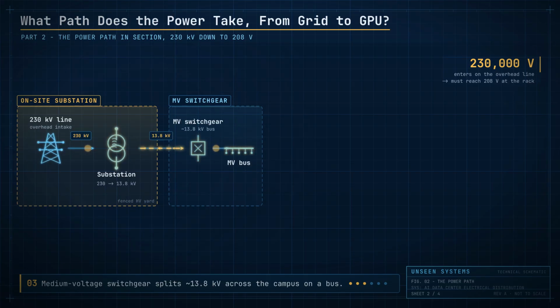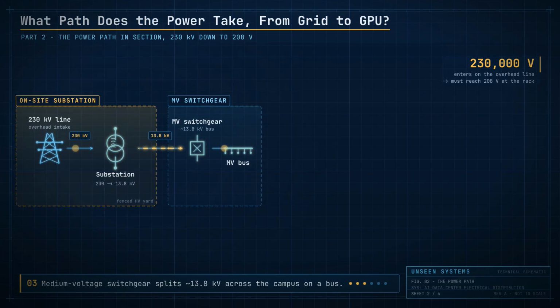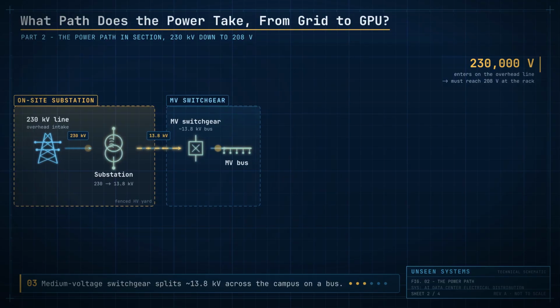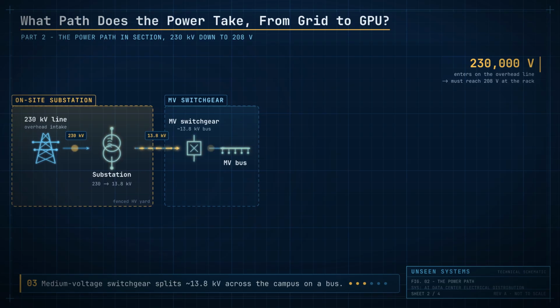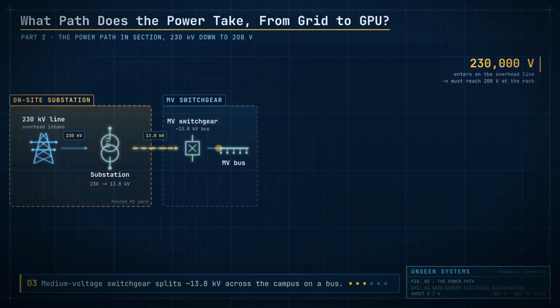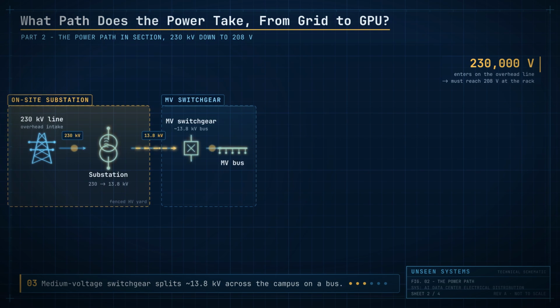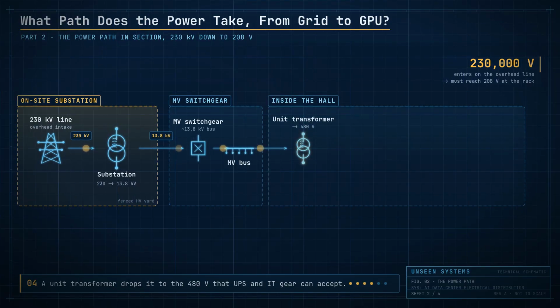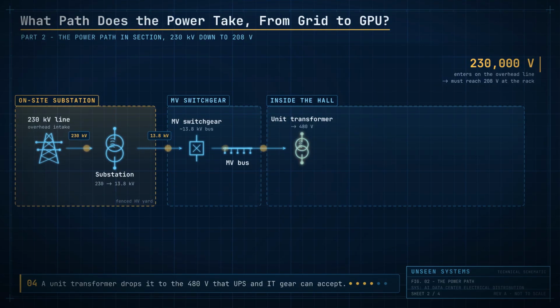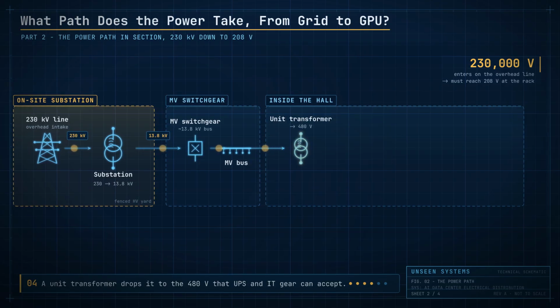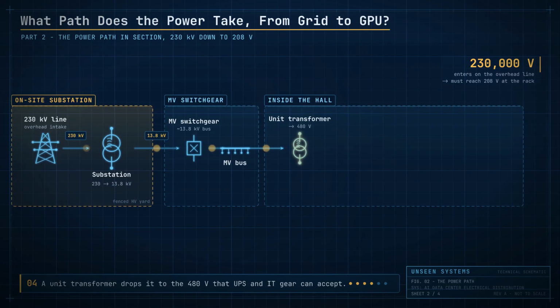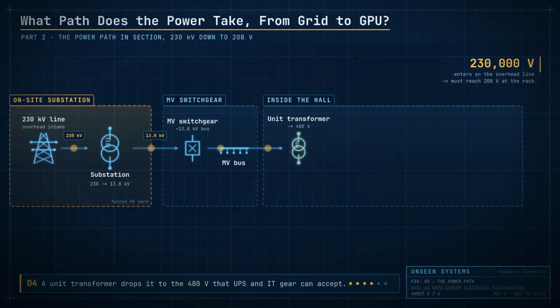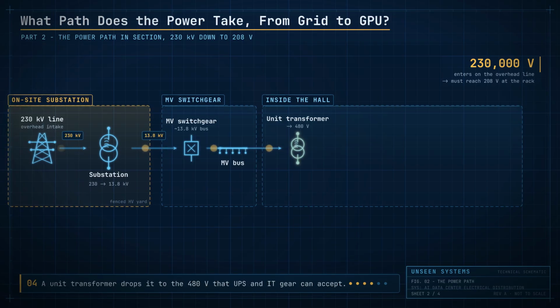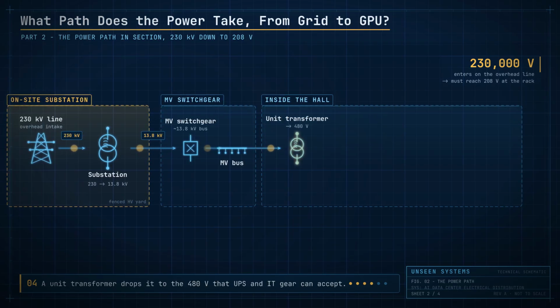Inside the medium voltage switchgear, that 13,800 volt supply is split onto a bus and fanned out across the campus, one incoming river of power, divided into the feeders that reach each building. Still far too high to touch, but low enough now to route around a site. Then at each building, a unit transformer drops that medium voltage again, down to 480 volts, the level the electrical gear inside can actually accept. The exact numbers shift from site to site, but the logic never does.